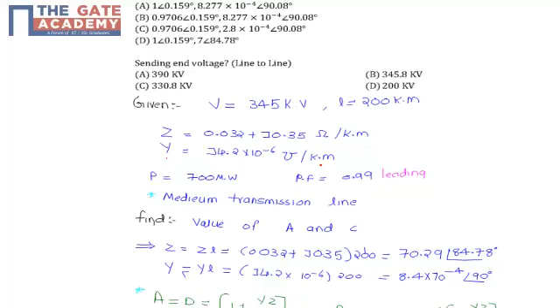Given full load receiving end of the line is 700 megawatts, which is nothing but power at the receiving end is 700 megawatts at 0.99 power factor leading, at 95% of rated voltage. Given rated voltage of 345 kV, it is 95% of the rated voltage, and we have to assume a medium length transmission line. We have to find the value of A and C, which are ABCD parameters, in the first part of the linked data question.